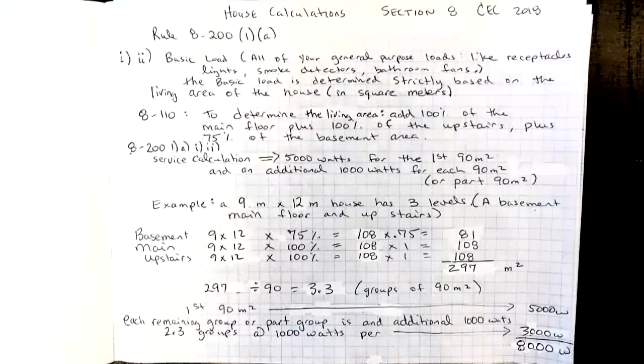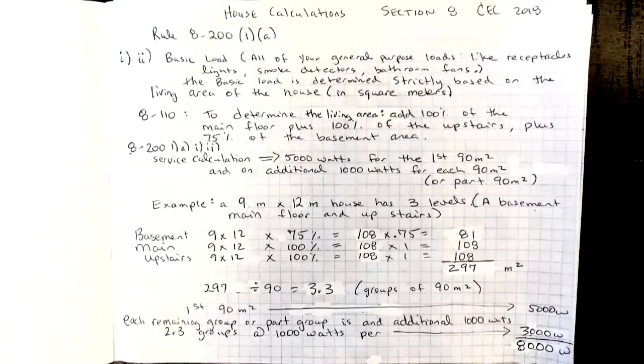So then moving on, 8-200-1A, items one and two, speak to how we actually apply the basic load to our service calculation. And what we do is we take a demand factor of 5,000 watts for the first 90 meters squared living area of the house and an additional 1,000 watts for each 90 meters squared or portion of 90 meters squared. So that means if you just have one meter squared left over, you would have to take a full 1,000 watts towards the demand factor.